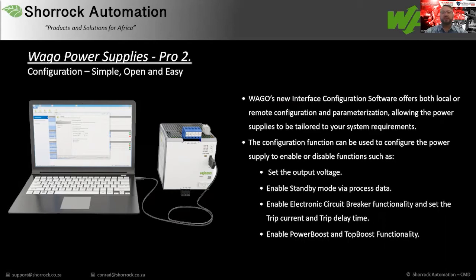The configuration function can be used to configure the power supply to enable and disable functions, such as we can set the output voltage. So whether you adjust it via the little push buttons on the front of the device, or alternatively, we can set up and say, this is exactly the voltage we want on this application. In addition, we can also enable the standby mode via process data. Also, this device has got an integrated electronic circuit breaker, which basically means we can set a trip current and a trip delay time for this device. This is particularly handy in applications where you have purchased a 40 amp power supply, for example, and then your current requirement is only 35 amps.